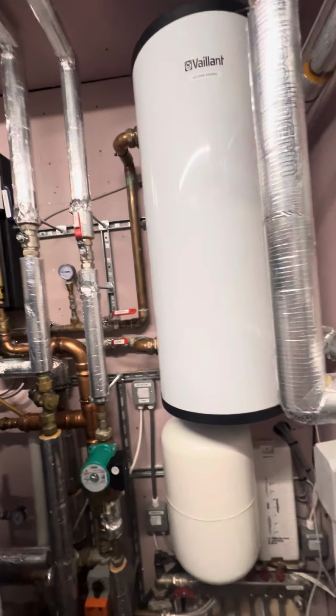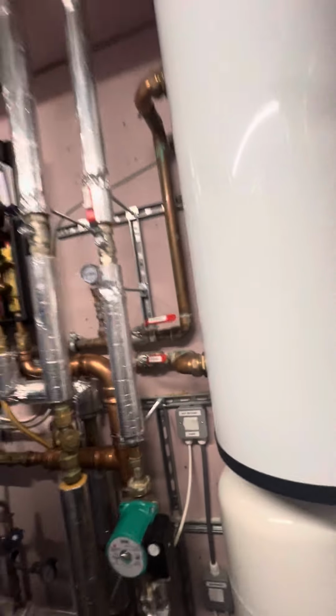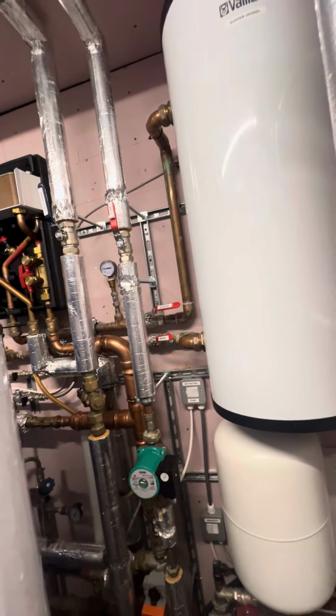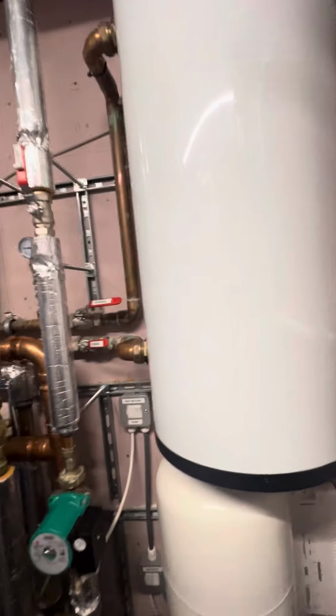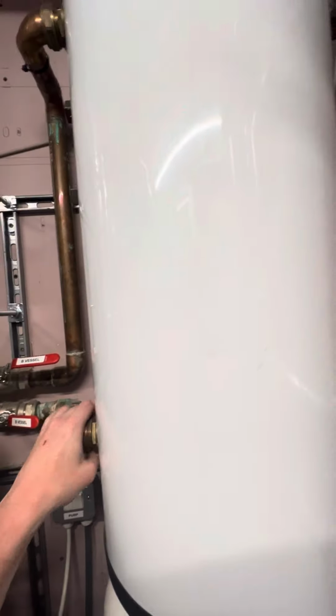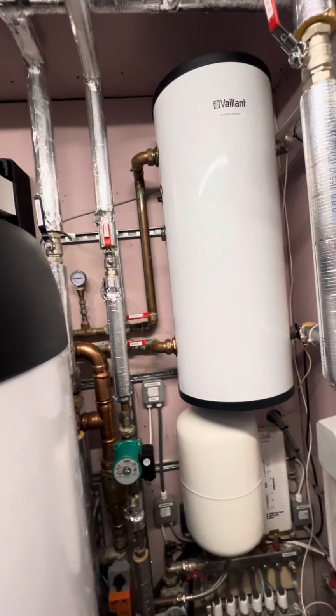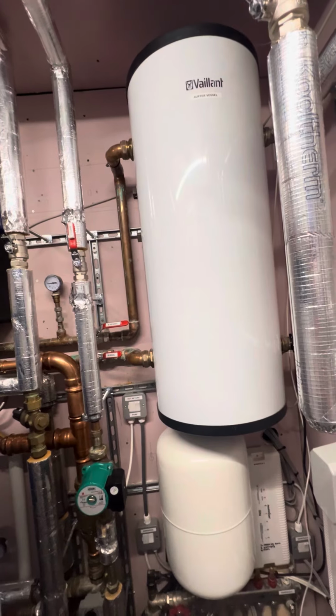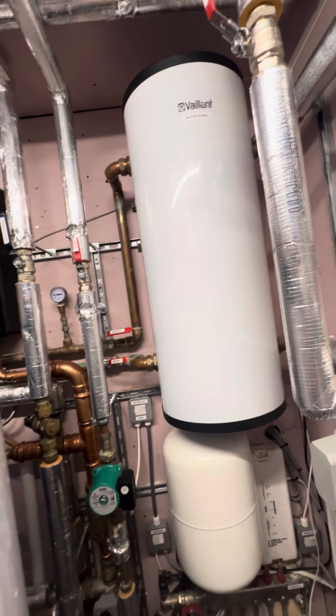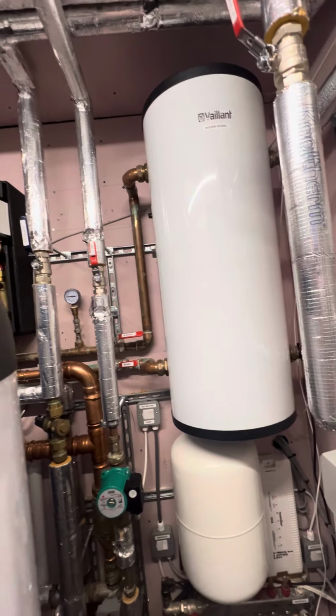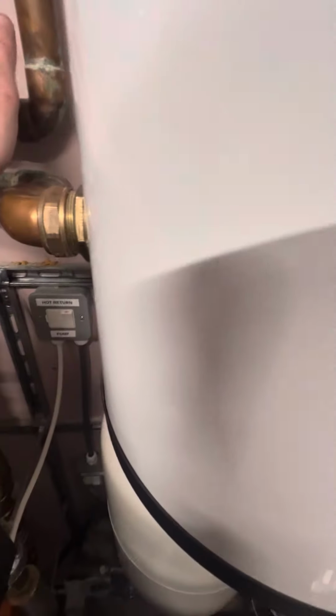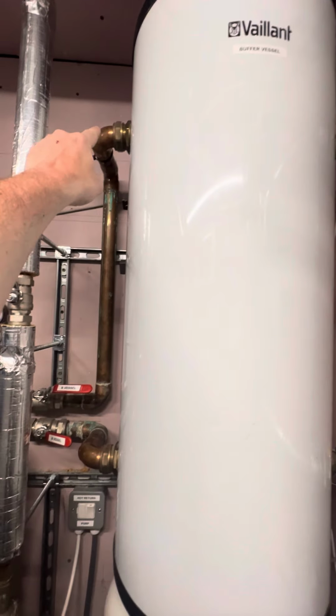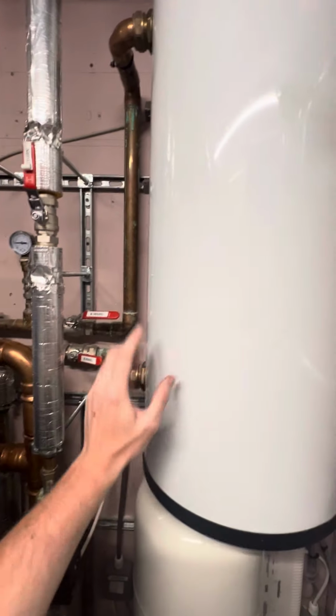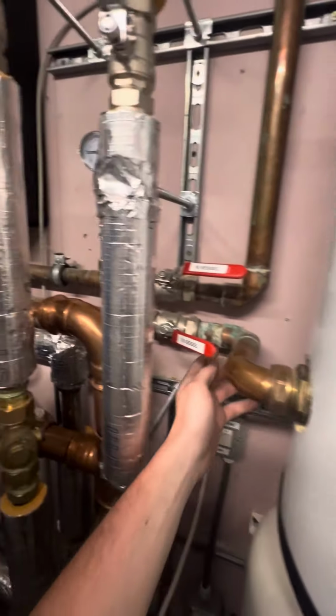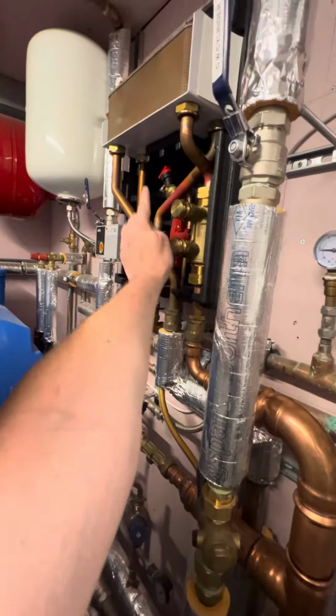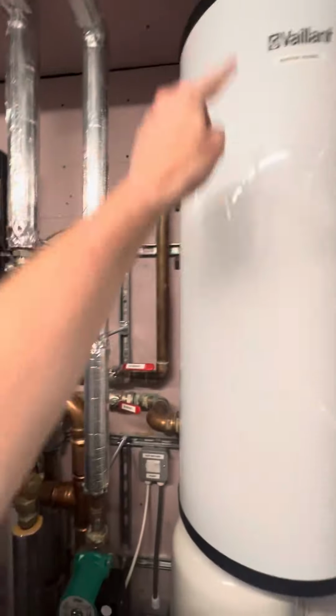So there's different ways of piping up buffer vessels if buffer vessels are required, so that you don't have as much efficiency loss, or you can balance the flows on either side of the circuits. There's lots of ways, which is a complicated subject of doing these buffers. Sometimes they're required, often they're not, but what matters is how you pipe it up, how you commission it, how you balance the system, as to whether it's going to reduce efficiency or actually serve a very good purpose and do what it's supposed to do. So from this upside of the buffer vessel here, we go into just down here. There's no separation here, it's all just one open chamber, and we flow back here and we go back to the other side of the plate heat exchanger. So we've got this pump here just pumping around the buffer vessel.